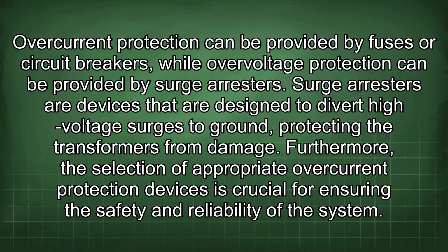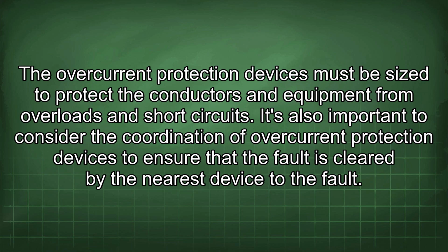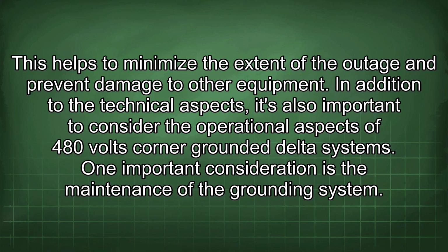Furthermore, the selection of appropriate overcurrent protection devices is crucial for ensuring the safety and reliability of the system. The overcurrent protection devices must be sized to protect the conductors and equipment from overloads and short circuits. It's also important to consider the coordination of overcurrent protection devices to ensure that the fault is cleared by the nearest device to the fault. This helps to minimize the extent of the outage and prevent damage to other equipment.